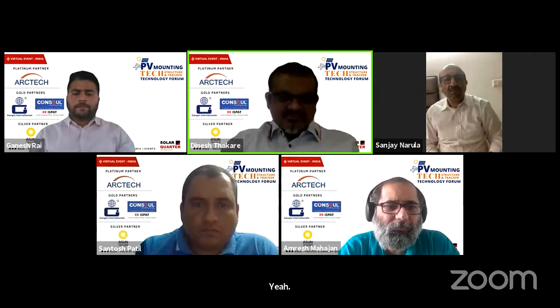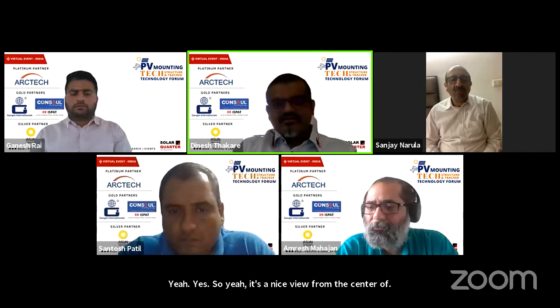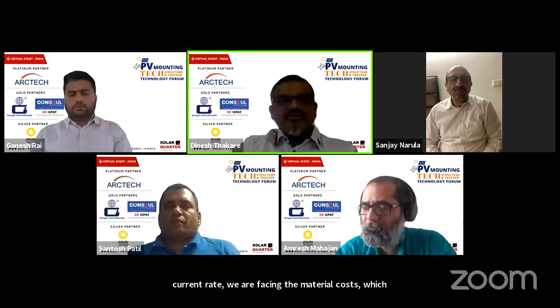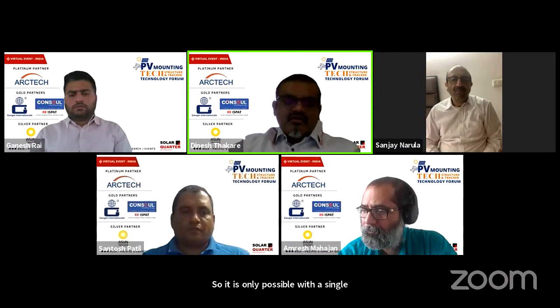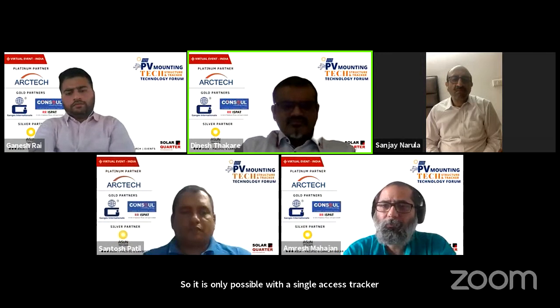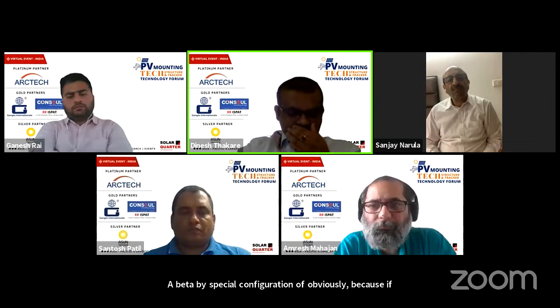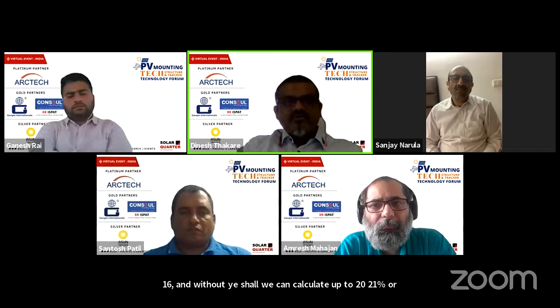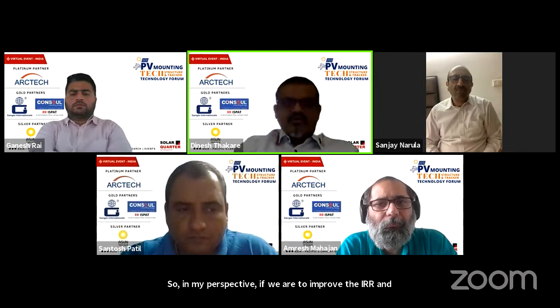Yeah, please. It's a nice view from Sanjay sir also, Rishi sir also. But I would like to say that in the current trend, we are facing module costs which are drastically increasing. So why can we not draw out the maximum energy from the module? It is only possible with the single axis tracker, with a bifacial configuration. If you compare with fixed tilt, the single axis tracker can already achieve 16% higher generation, and with bifacial we can calculate up to 20-21% higher generation. So in my perspective, if we have to improve the IRR and reduce the LCOE, I think tracker is the best option with the current trend.